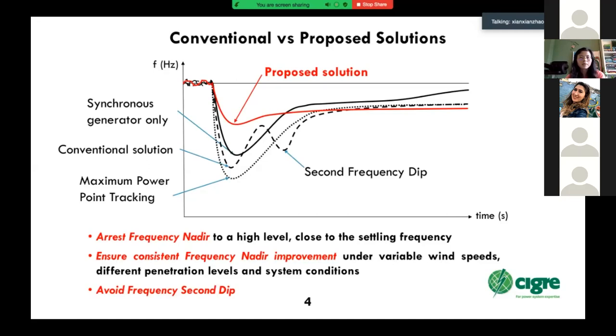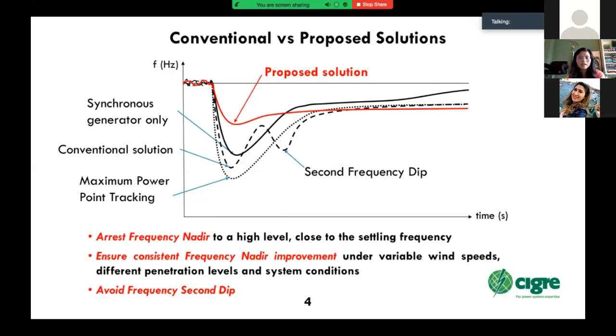The red line shows the proposed solution. We can see that the frequency nadir is greatly raised close to the settling frequency, and there is no secondary frequency dip. This can be realized because there is no recovery during the primary frequency control. The recovery will be automatically realized in the secondary frequency control. In this way, the frequency nadir can be raised to a high level because more energy can be released.